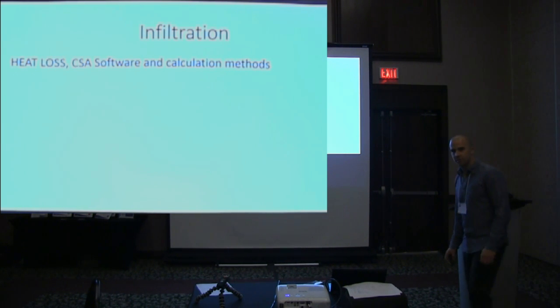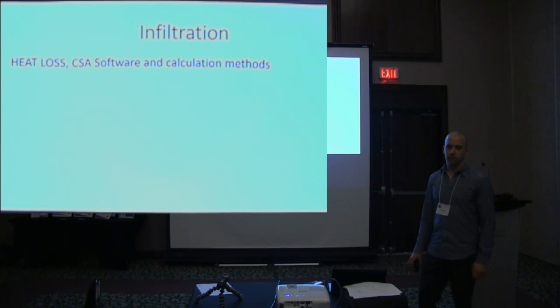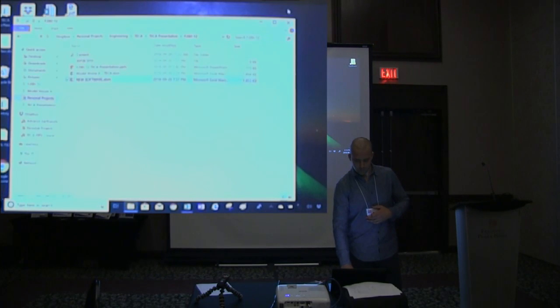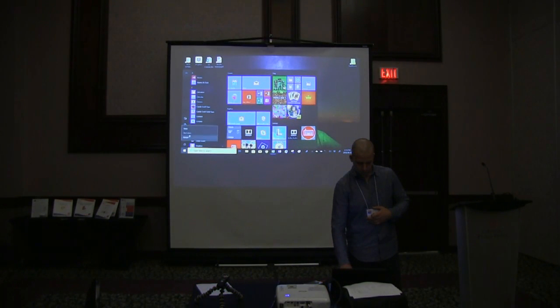Well, we did a renovation in Surrey, and they called in a mechanical engineer to do the heat loss. I had heat in every room in the house. The engineer came in and said, well, because it's an interior condo, we didn't need heat in the bathroom, or walk-in closets, or a powder room, or any of this. Well, if it's a top floor, you don't lose upward. If it's a middle floor, two levels, it's a powder room, there is no loss. No, but she had one six-inch run through the whole main floor, basically. Sounds like a poor way to do business. So the engineer called.